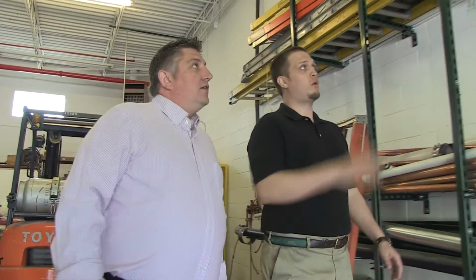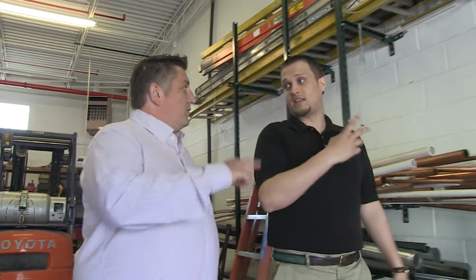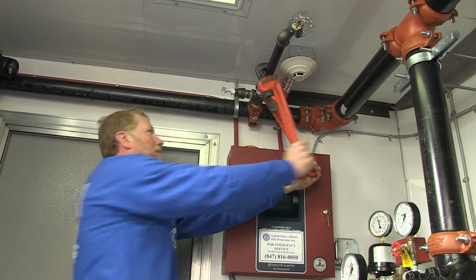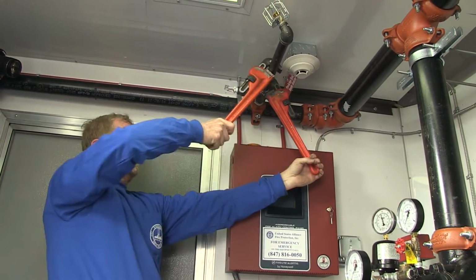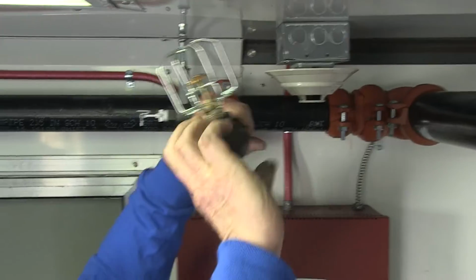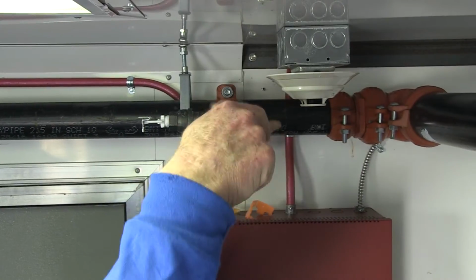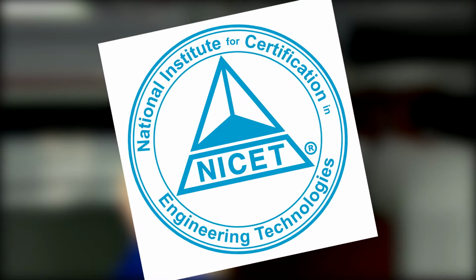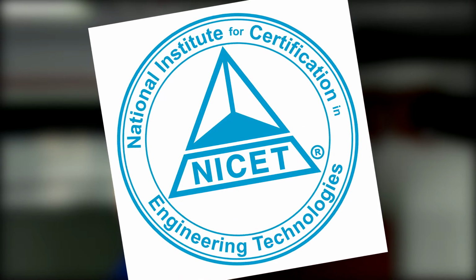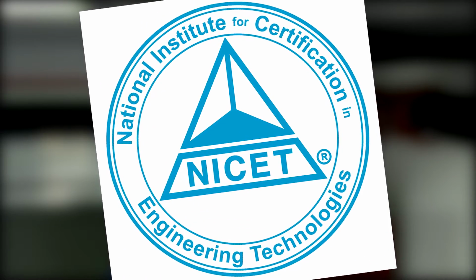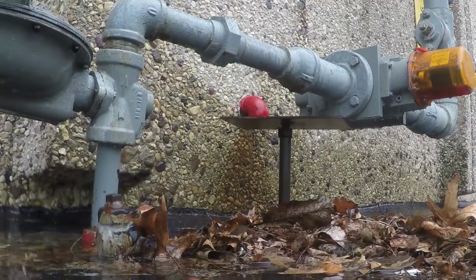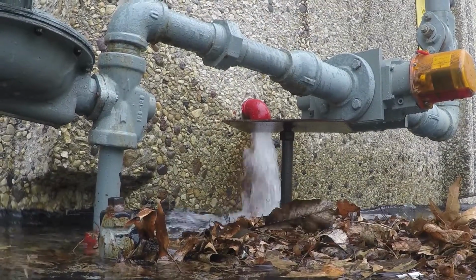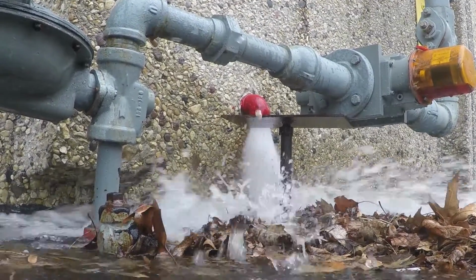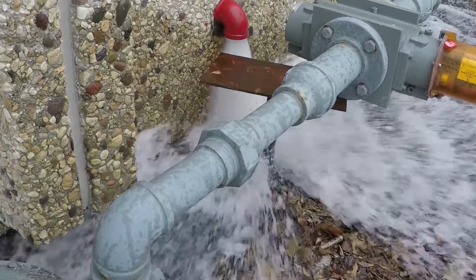Here are your responsibilities or those of the designated representative. Of greatest importance, you may only hire qualified personnel for ITM activities. In Illinois, the law requires you hire an individual or company that has NICET Level 2 certification and/or has completed a certified sprinkler fitter apprenticeship program. Be sure to coordinate with that person to minimize any water damage caused by the discharge of water during ITM activities.